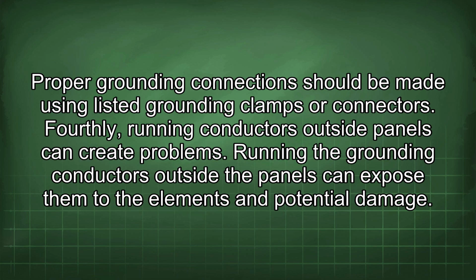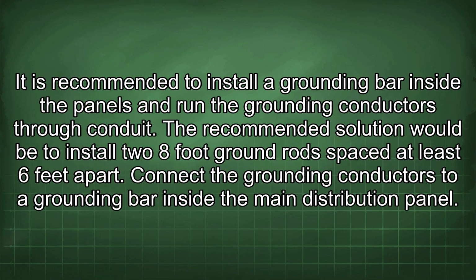Fourthly, running conductors outside panels can create problems. Running the grounding conductors outside the panels can expose them to the elements and potential damage. It is recommended to install a grounding bar inside the panels and run the grounding conductors through conduit.